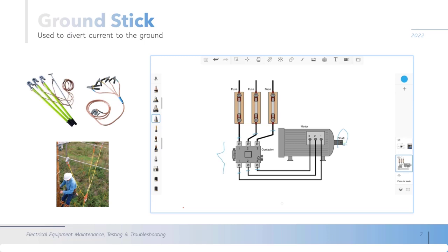So in order to work in the terminals you need to cut the voltage. So you send an order to the control circuit and you open this contactor. So in this case you will have no voltage here, here and here, but you will have voltage here. I will say this is voltage 1. So here you will have 0 volts.